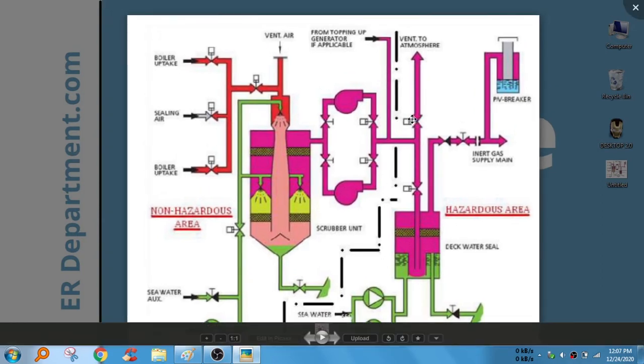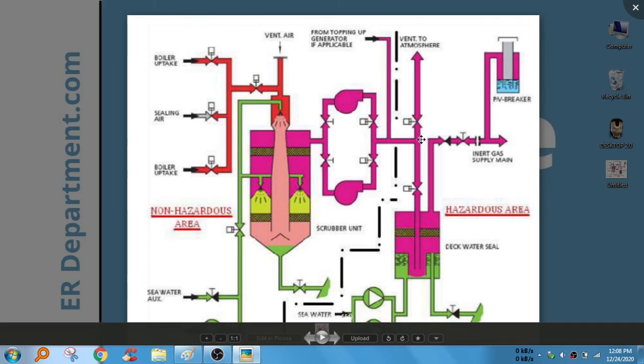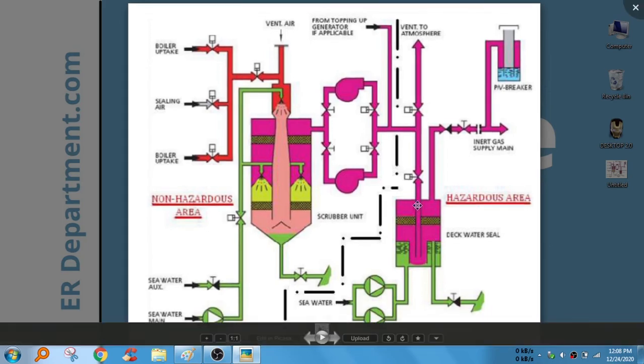Here also you have to note one more thing that there is an automatic valve arrangement system here given, which basically is if the oxygen content goes above 8 percentage then this valve opens. There will be a three-way valve or some arrangement and it will be given to the atmosphere. And if it is below 8 percentage then it closes and it goes to the deck seal. It's commonly called as deck seal.